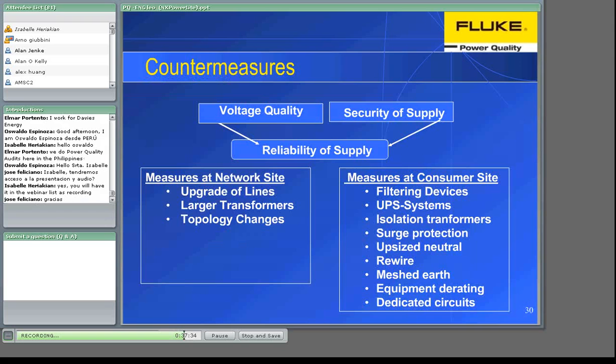Countermeasures. First of all, it is important to say that there is no single solution to power quality problems. For each type of problem, there is a range of possible mitigation. In the real world, it is likely that several problems will coexist, and the solutions adopted must be compatible with each other. It is also important to realize that the network is dynamic. A large office building, for instance, may have hundreds of changes per year, so the harmonic spectrum changes continuously.